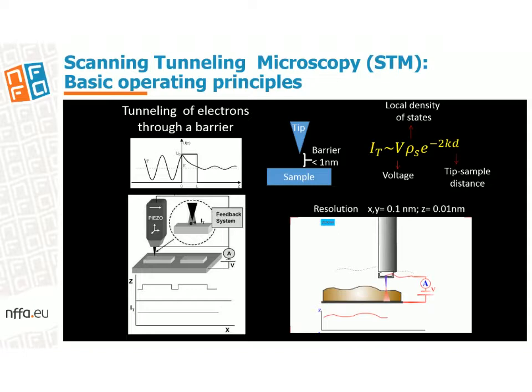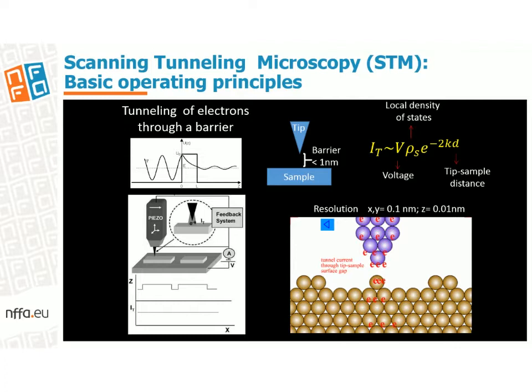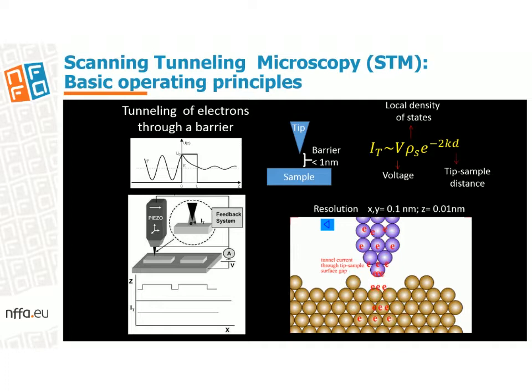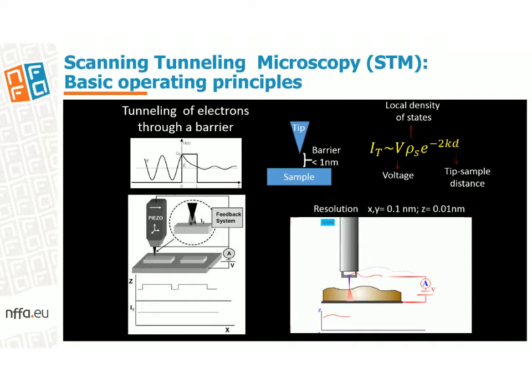STM is based on the quantum phenomenon of the tunnel effect, in which electrons can penetrate potential energy barriers. In this technique, a tunneling current can be established through a barrier gap by locating a sharp conductive tip at a few angstroms away from the sample and by applying a voltage between tip and sample. The tunneling current is directly proportional to the applied voltage, the local electronic density of states close to the Fermi level, and exhibits an exponential dependence with the gap distance, which is the key for the high sensitivity of the STM.